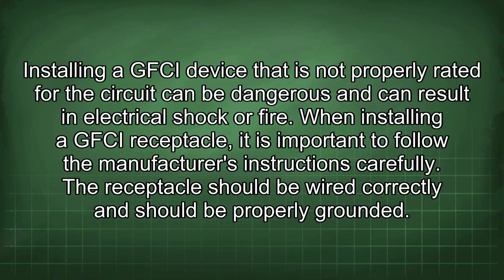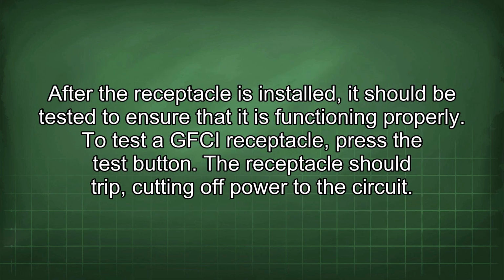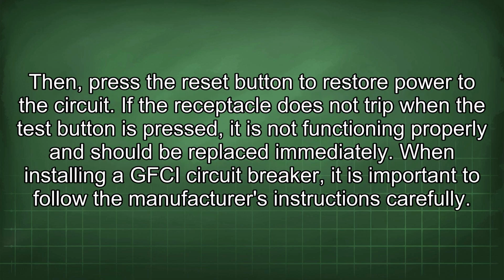electrical shock or fire. When installing a GFCI receptacle, it is important to follow the manufacturer's instructions carefully. The receptacle should be wired correctly and should be properly grounded. After the receptacle is installed, it should be tested to ensure that it is functioning properly. To test a GFCI receptacle, press the test button. The receptacle should trip, cutting off power to the circuit. Then press the reset button to restore power to the circuit.